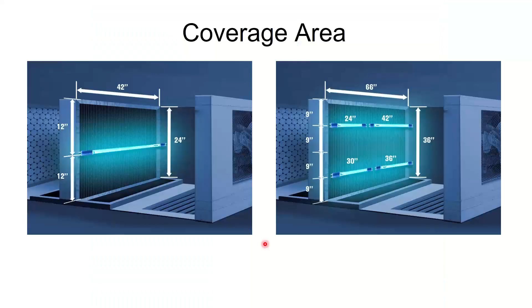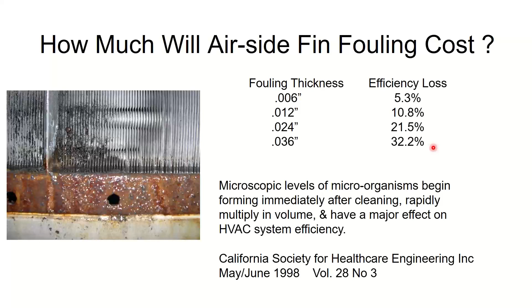In addition to keeping gross things from growing on your coil, like bacteria and mold, keeping debris off your coil also makes it better for heat transfer. If my coil's dirty, the coil has to heat up or cool down the mold, and then the mold has to heat the air. That takes longer, so it runs my compressor longer. Additionally, it's harder to push air through a coil that has stuff growing on it.